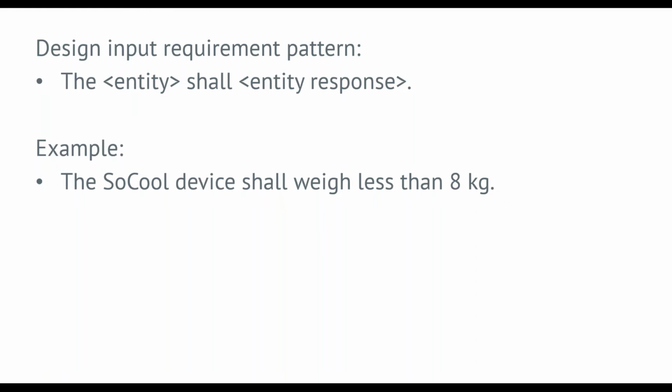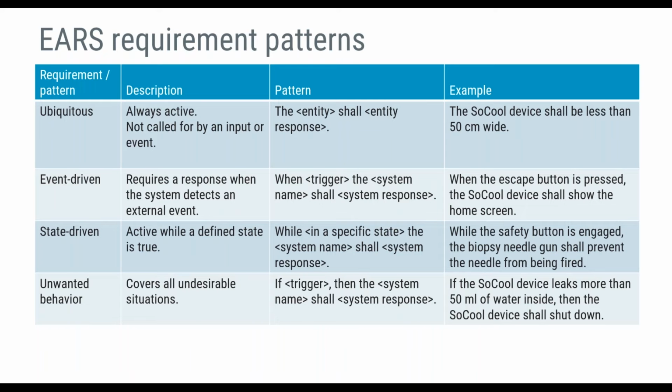So that's where EARS come back to us and come into play, because EARS has a number of patterns that you can use in conjunction with events or different states or even unwanted behaviors. And we have examples of that here, the event-driven one: when the escape button is pressed, the SoCool device shall show the home screen, for example.